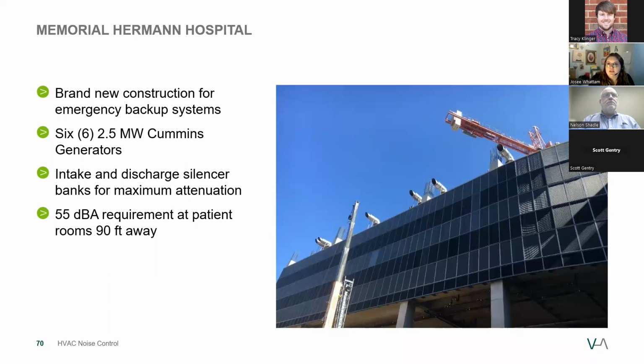This is an example project at Memorial Hermann Hospital in Houston, Texas. It involves the brand new construction of an emergency backup system. Six 2.5 megawatt Cummins generators were installed on this project. Vibro-Acoustics designed the intake and discharge silencer banks for maximum attenuation. The requirement was maximum 55 dBA perceived at patient rooms 90 feet away from the air intake and exhaust walls.